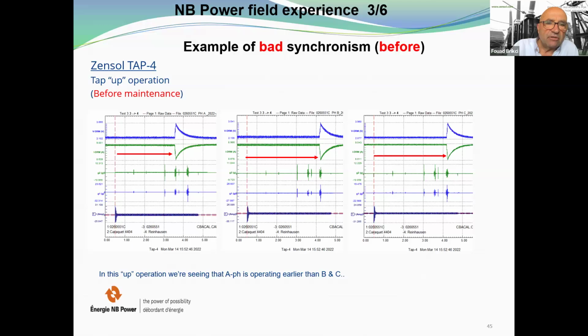before maintenance. Here you can see on the bottom the current for phase A, current phase B, current phase C. On the left, they put two accelerometers, and on the green, they put the current and the voltage that they have recorded from the DRM accessory. And here you can see that the diverter switch for phase A is operating earlier than phase B and phase C. And this is done thanks to the current.